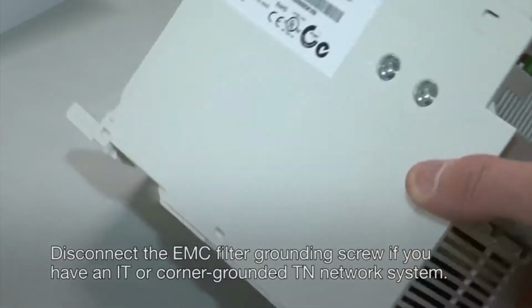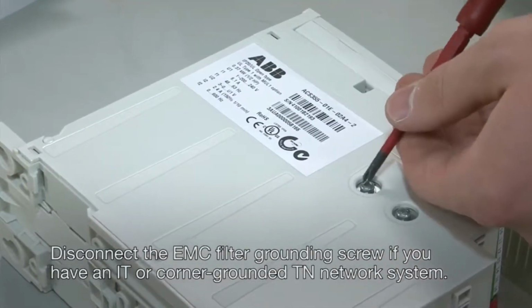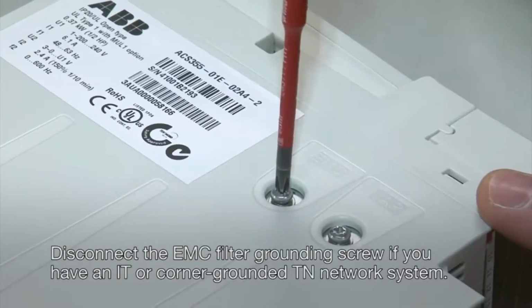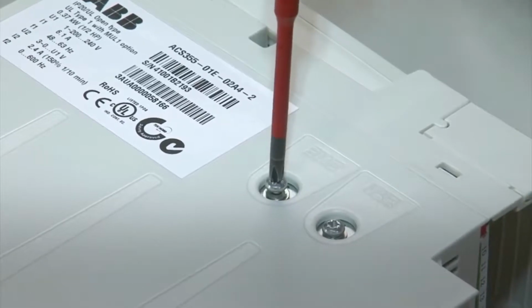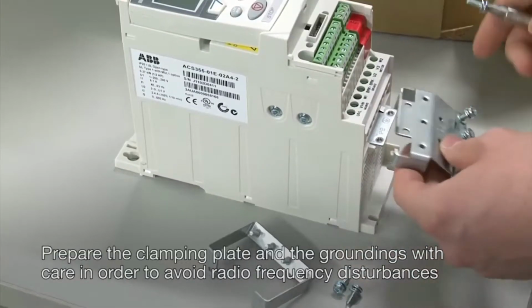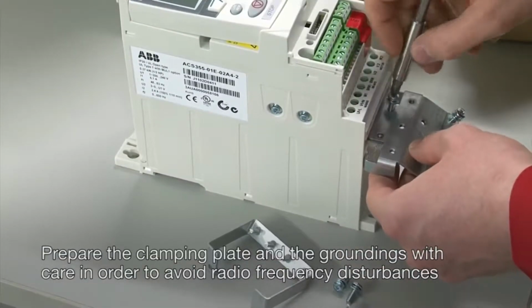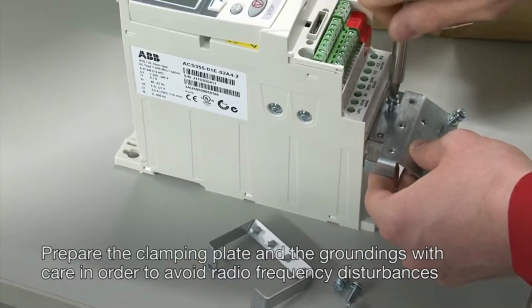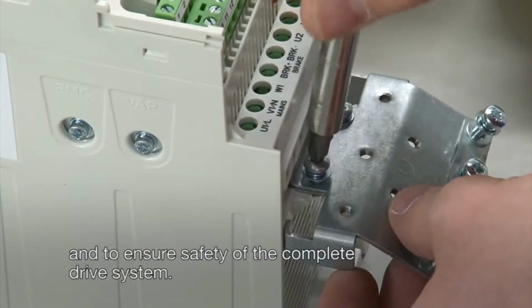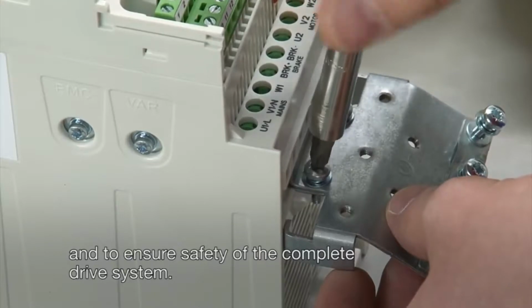Disconnect the EMC filter grounding screw if you have an IT or corner-grounded TN network system. Prepare the clamping plate and the groundings with care in order to avoid radio frequency disturbances and to ensure safety of the complete drive system.